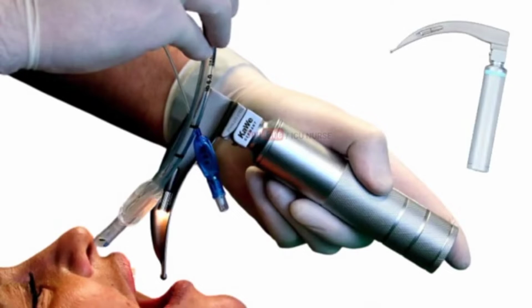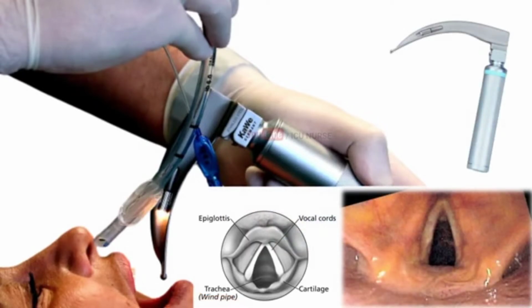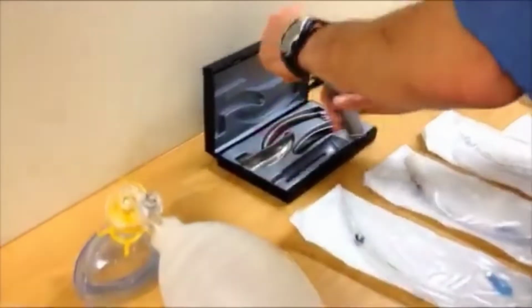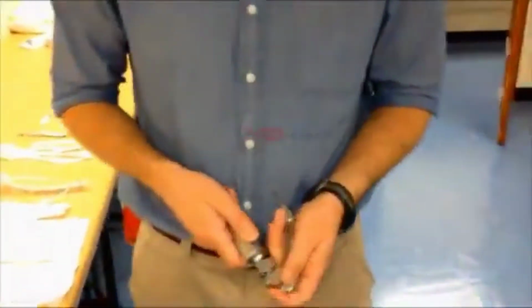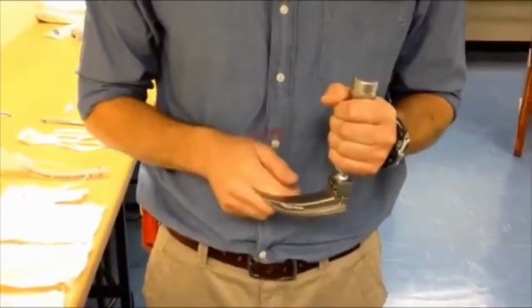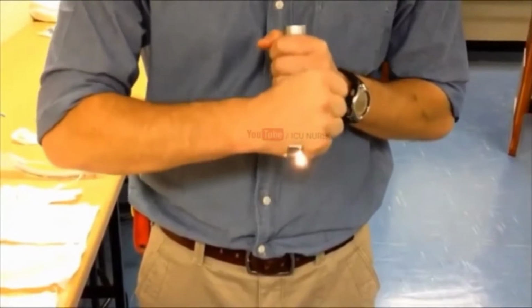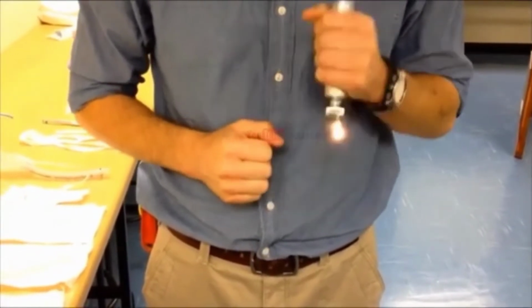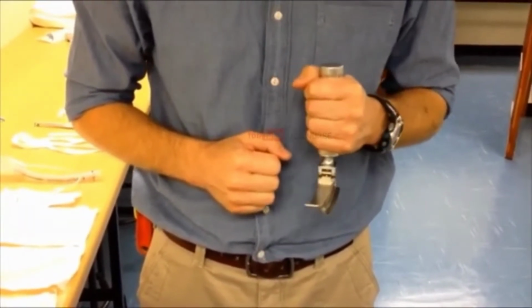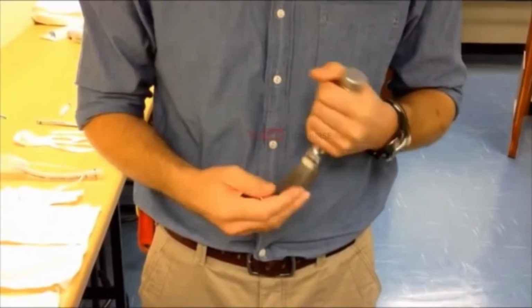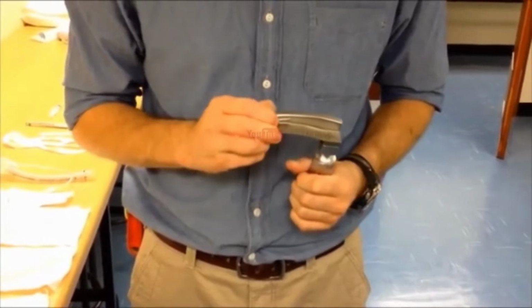Laryngoscope. Laryngoscope is used to expose the laryngeal inlet under direct vision or line of sight to facilitate placement of tracheal tube beyond the vocal cords. Check if the blade fits properly with the handle. Check if the light source is working properly even when the blade is stretched. Make sure that there are no jiggly parts in the laryngoscope. The laryngoscope should be sturdy. Ensure that the bulb is tightly screwed and not jiggling.